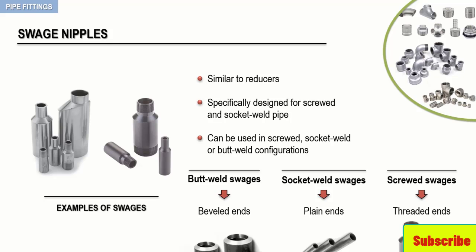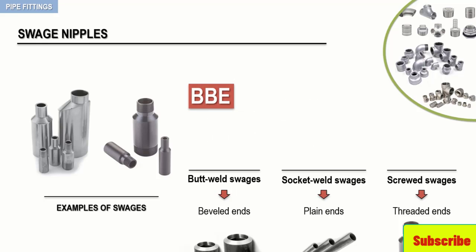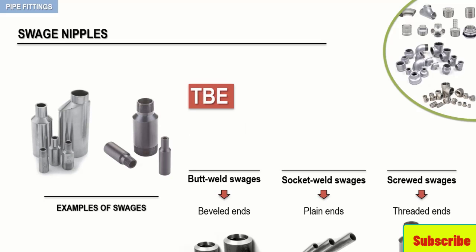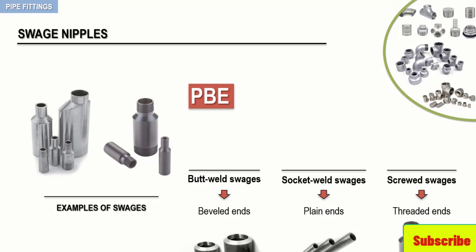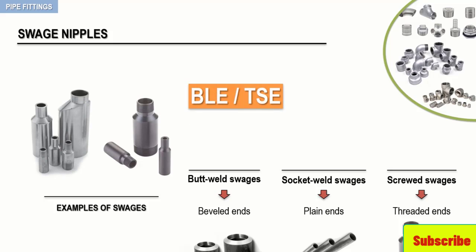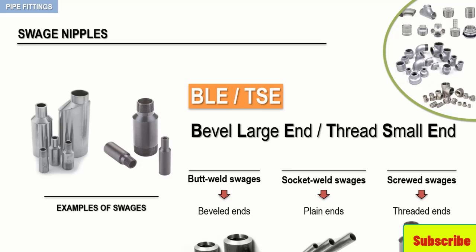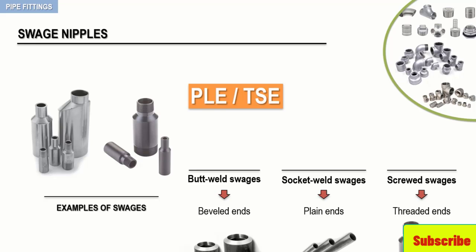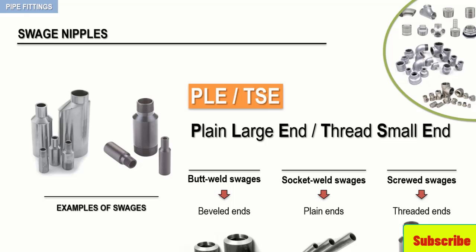Swages are also manufactured with different preparations on their opposing ends. When specifying a swage, you must use one of the following abbreviations: BBE for Bevel Both Ends, TBE for Thread Both Ends, PBE for Plain Both Ends, BLE TSE for Bevel Large Ends Thread Small Ends, and finally PLE TSE for Plain Large Ends Thread Small Ends, as in this example.